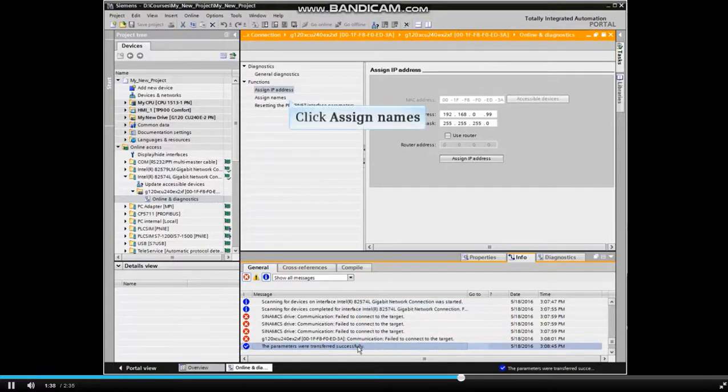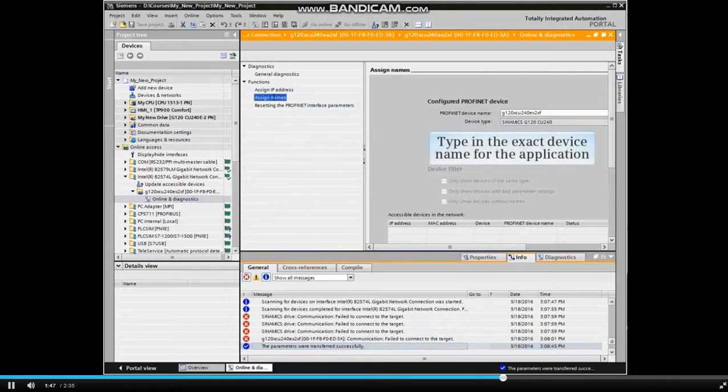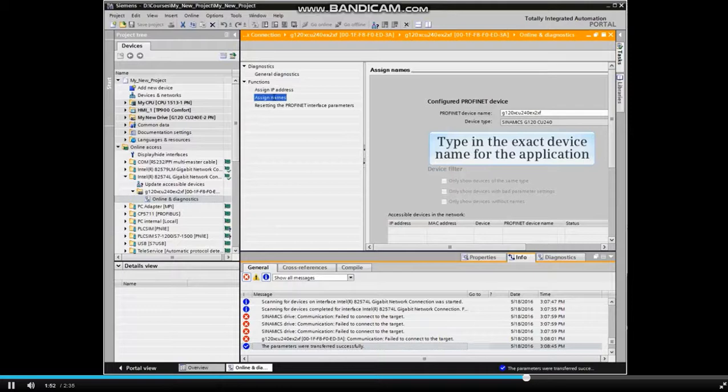Now we will assign the correct device name to allow communication via PROFINET. Click Assign Names from the Functions menu. In the PROFINET device name entry box, type in the exact device name for the application.